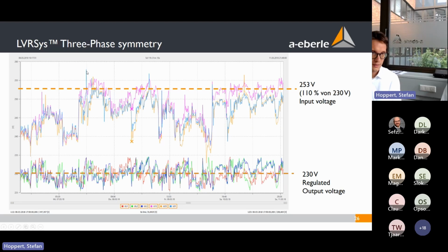You see here, it's regulated more or less 10% down. And that's, for the factory, it's good. And besides this, the three phases are important that they are symmetric. If you see here between the phase L1, the pink line, and the L2 are 9 volts difference. This makes a big problem for engines like mills, all three-phase engines. They have problems if they have unsymmetric amplitudes of the voltage. And with our regulator, we can stabilize this because it's possible to regulate each phase separately.